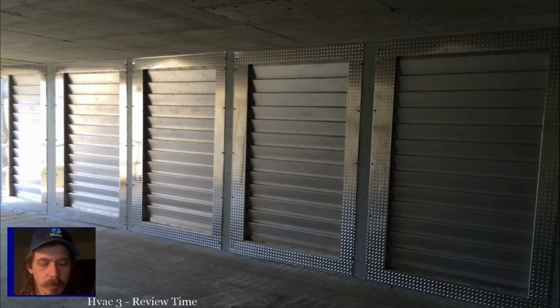All right, the speed control of an ECM is controlled by the electronics in the motor control section, and it's intrinsically linked with the motor, the control circuit, the control board. The ECMs are programmed to match up with the control board of specific equipment and the cabinet sizes and things like that. And I think it's way less complicated than they would make you believe if you sit through a manufacturer's class on it. But the point still is that an ECM motor is programmed to be with a certain piece of equipment, and replacements have to be programmed like that.